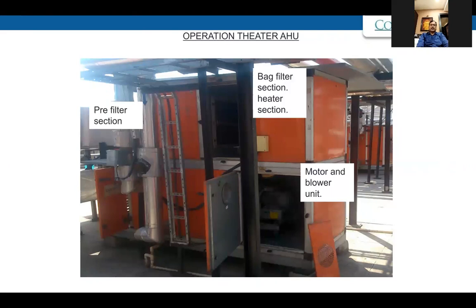Wherever you go for inspection, or within your hospital also, you can open and see for yourself how it functions. The motor has to be of a particular capacity, then only it can have a blower designed to work with that motor. Pre-filter section will have a crude filter which will filter the incoming air, and then the bag filter section which is micro V filter. And the HEPA filters generally are placed inside the operation theater. Only in general OT we have permitted that they can be within the AHU also.